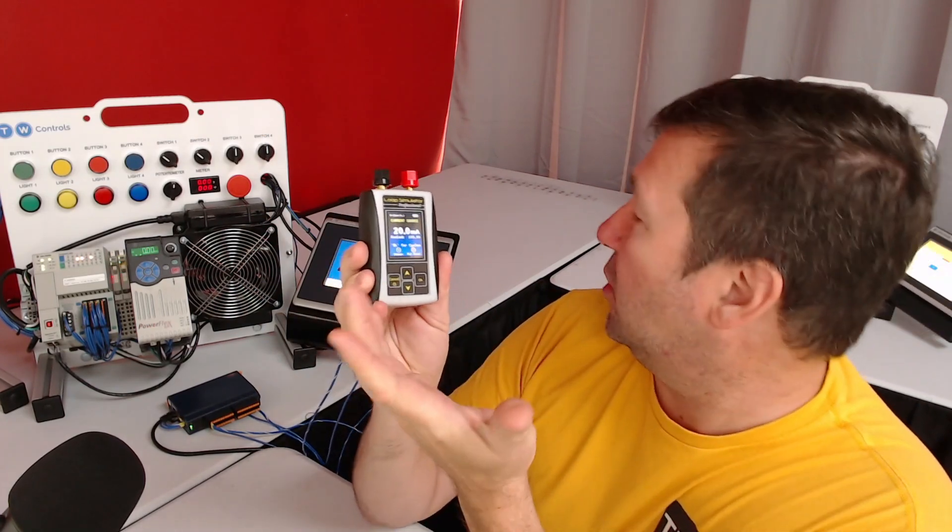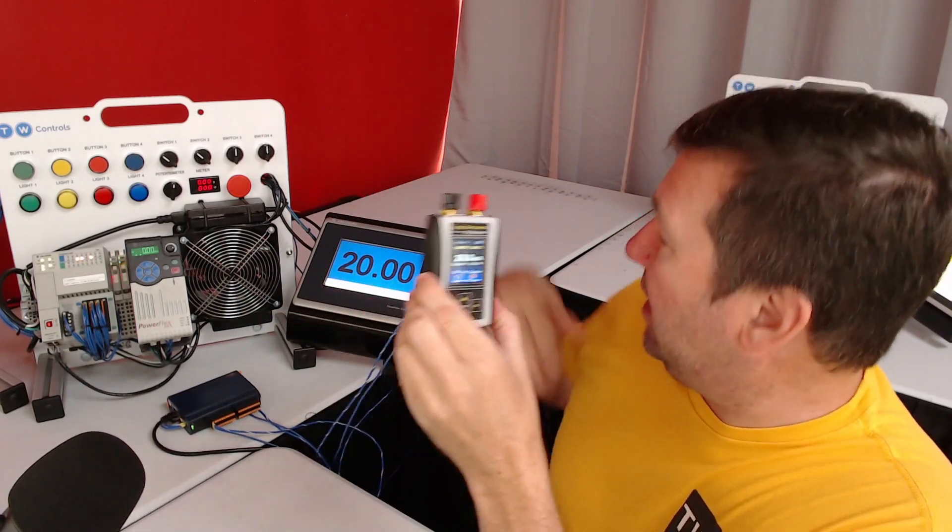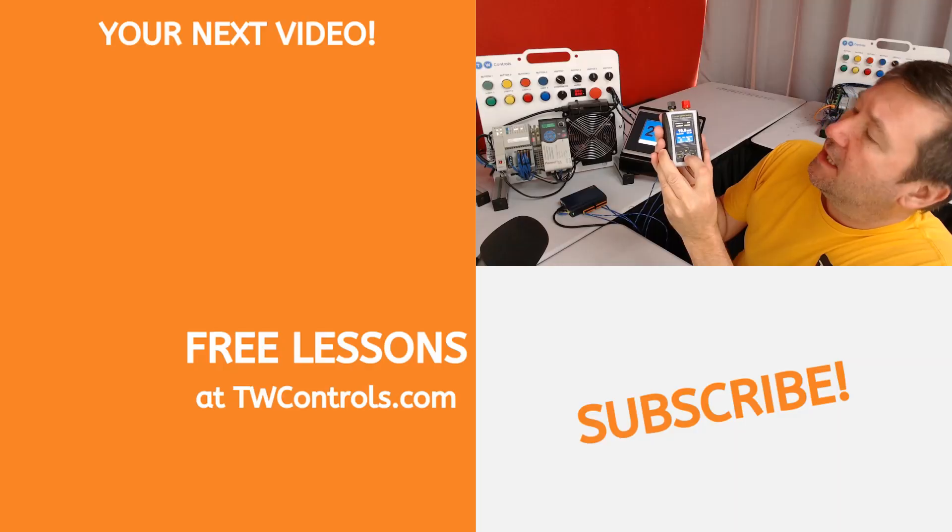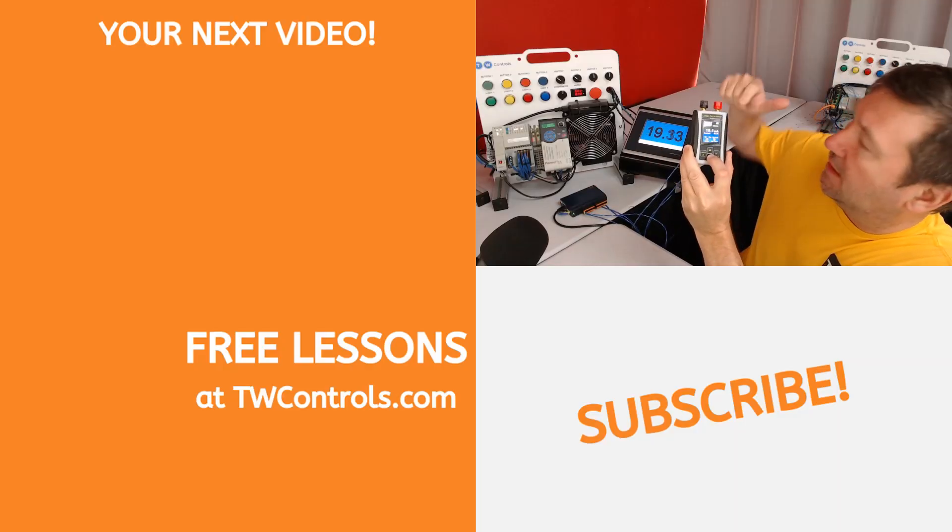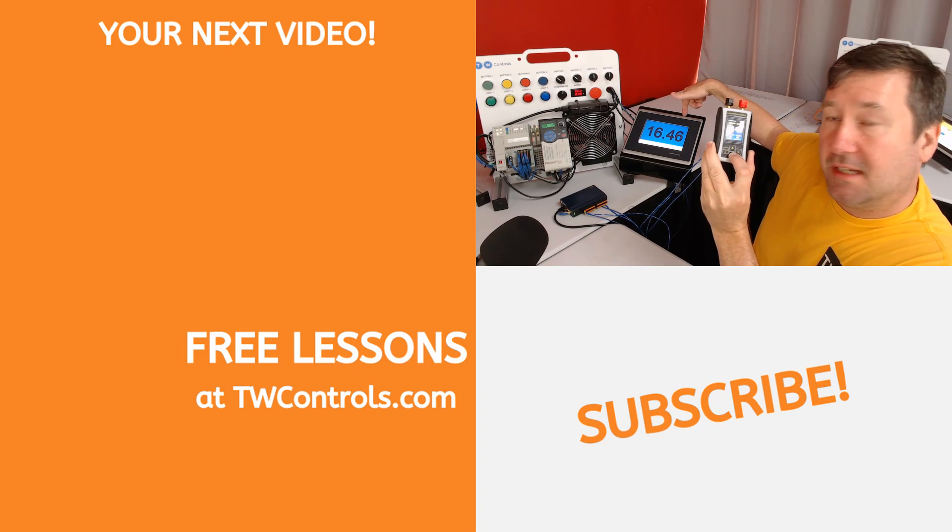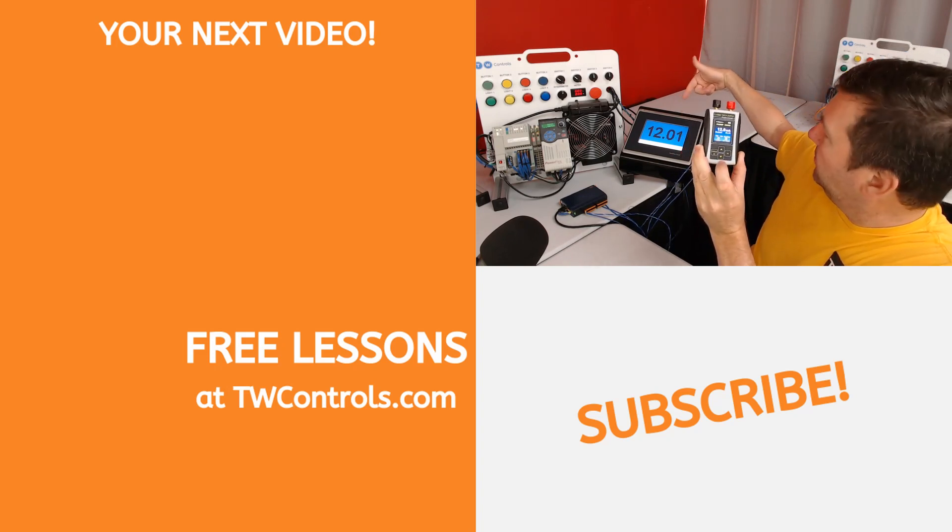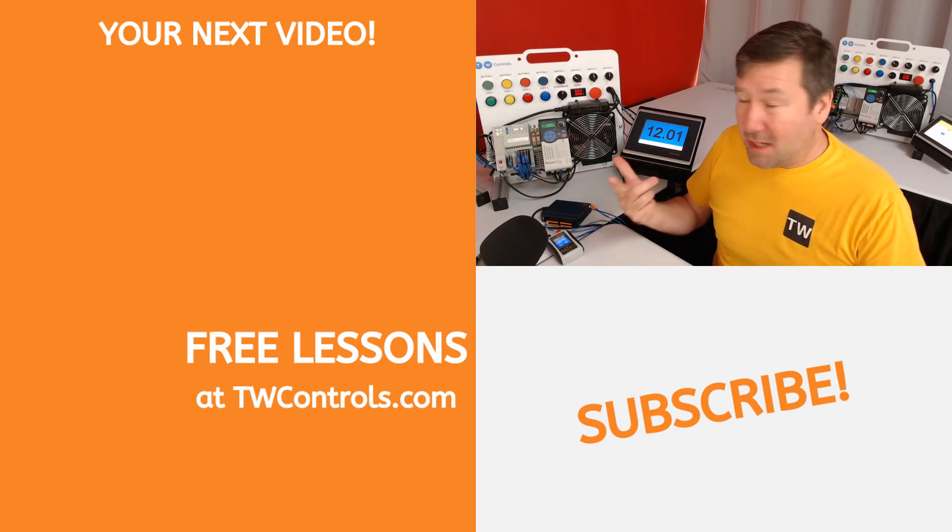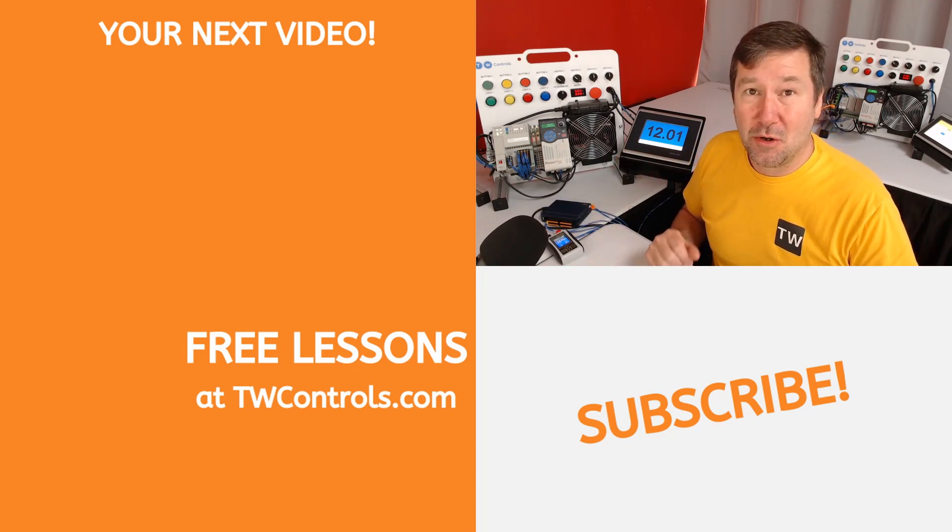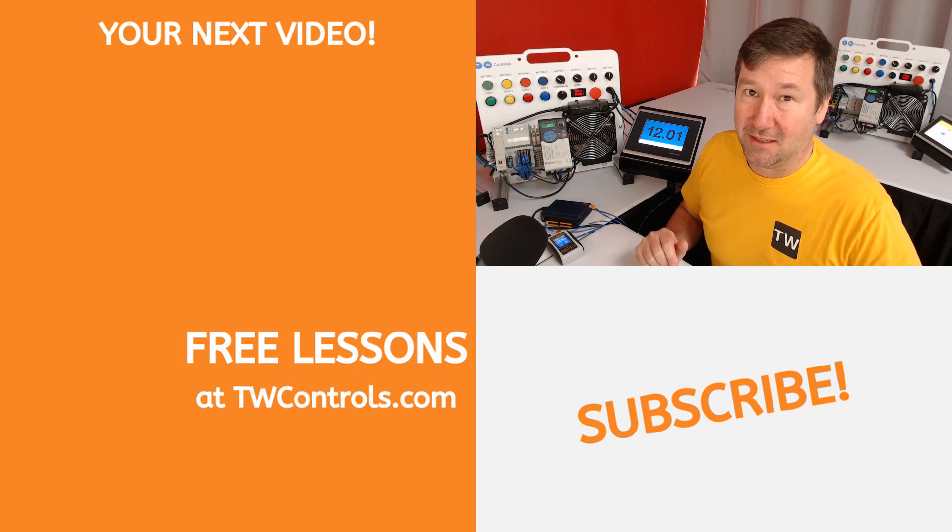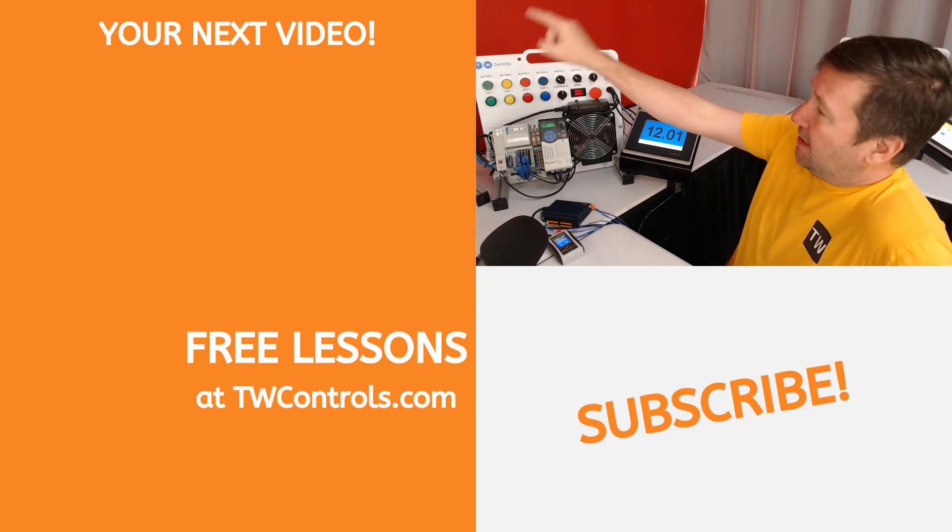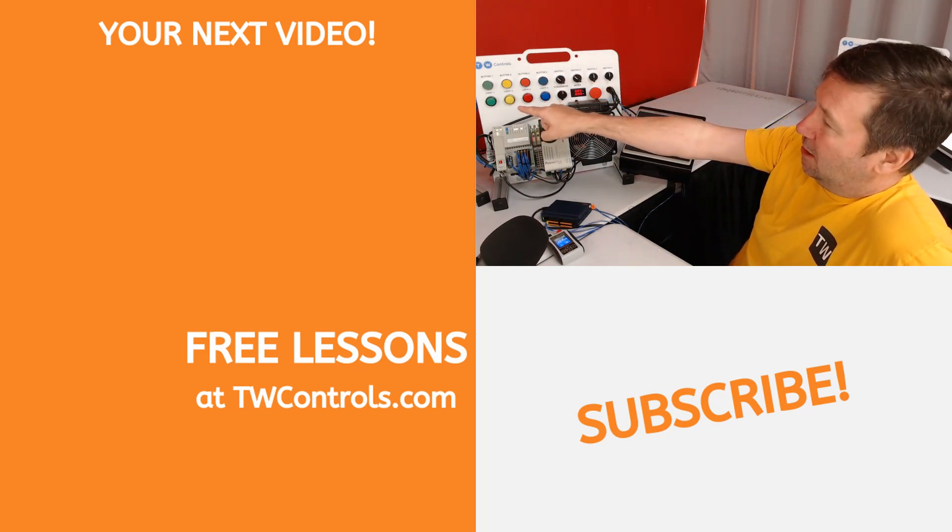We're going to start out at 20 here and yeah we're showing 20 there. I can bring it down and we can see it matches up nicely with that so I'll just stop here at 12 and we're at 12.01. Now if you don't have a display or even if you do you still need to know a little bit about troubleshooting analog signals so I've created this playlist to help you out.